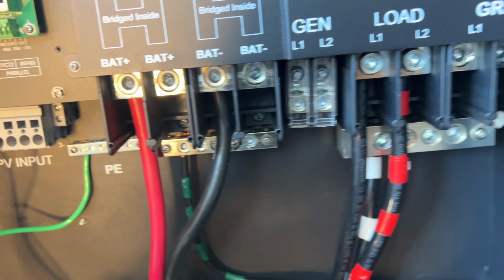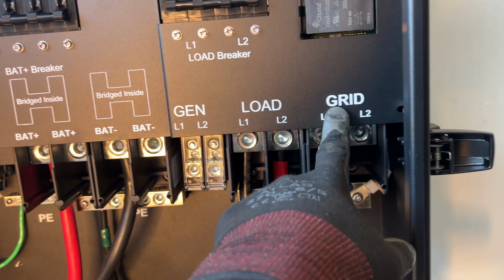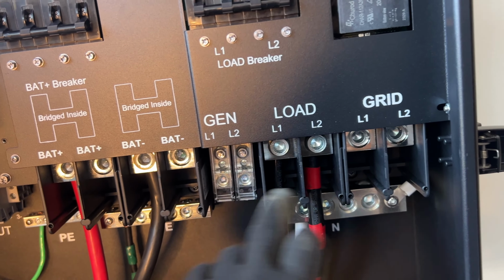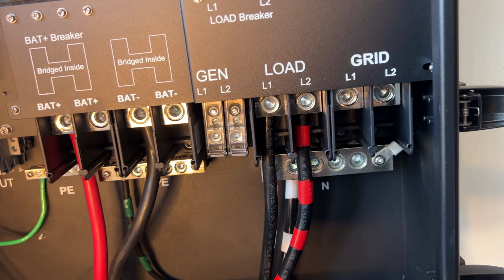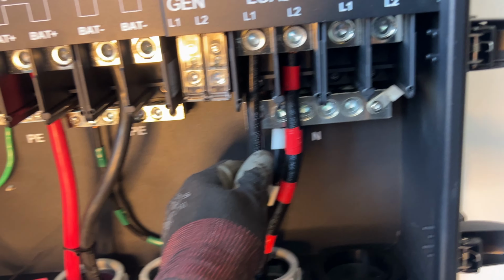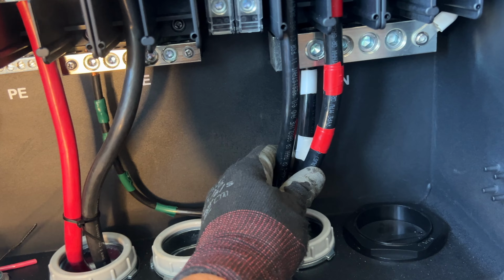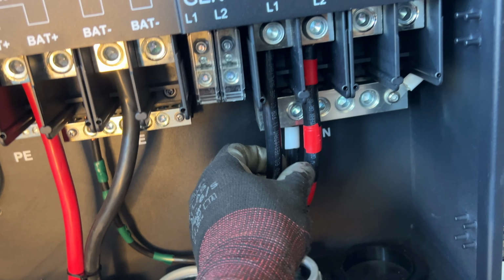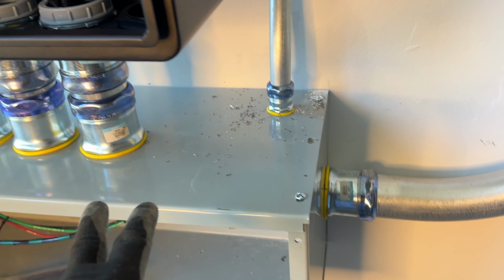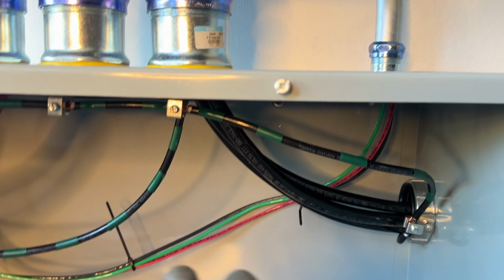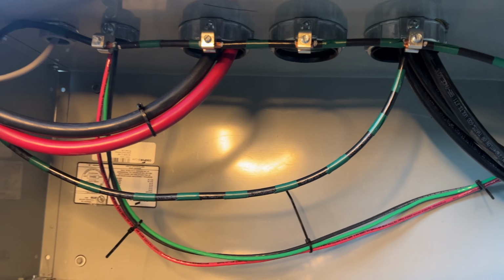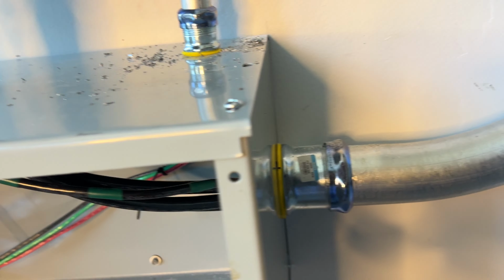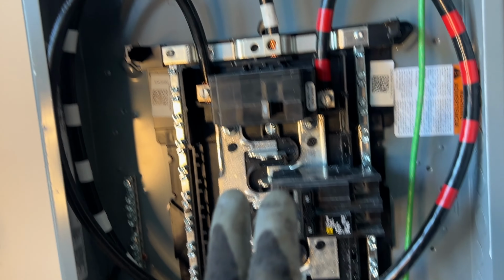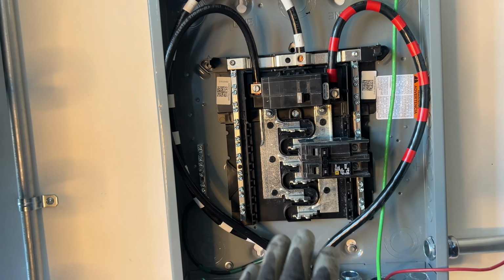This system does not have any grid power or a generator, so those terminals are all blank. The backup panel has 2-aught copper for line 1, line 2, and neutral running through the gutter, as well as a ground wire that grounds all of the bushings that run through this conduit and then comes up here and feeds this panel.